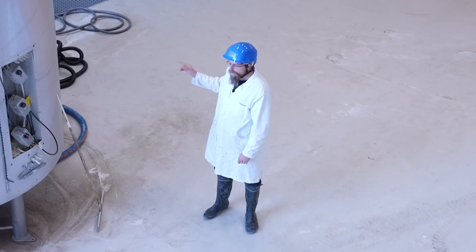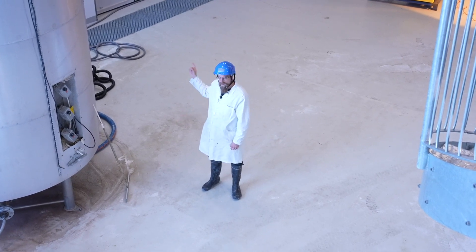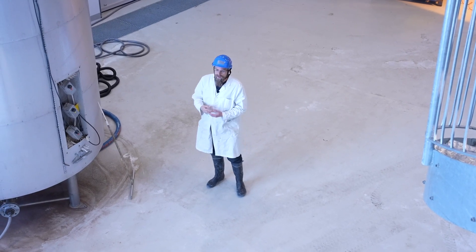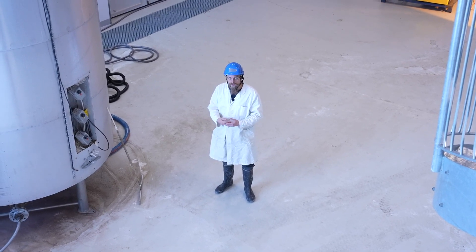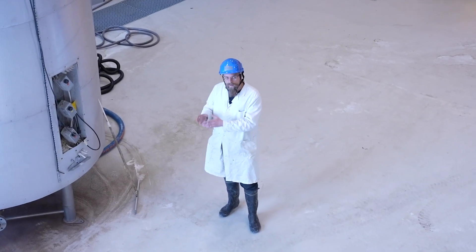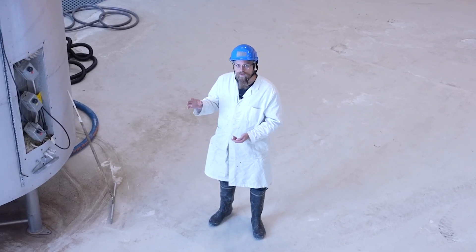This is the NP Harvest pilot equipment and process. The water that we're treating right now is black water — that means it's pee and poo. There's a digester behind that wall which treats it first, recovering biogas from the material, which means energy recovery. But it's still rich in nutrients: ammonia and nitrogen, and phosphorus in the form of soluble phosphate. And that is what we want to recover here.